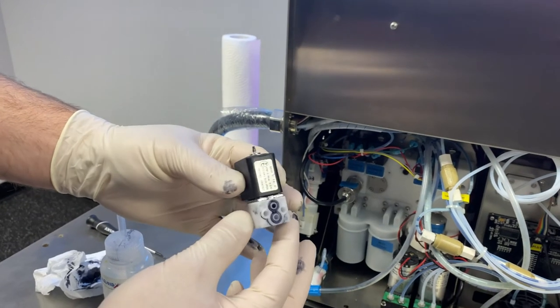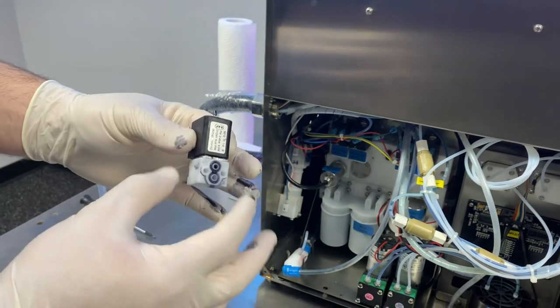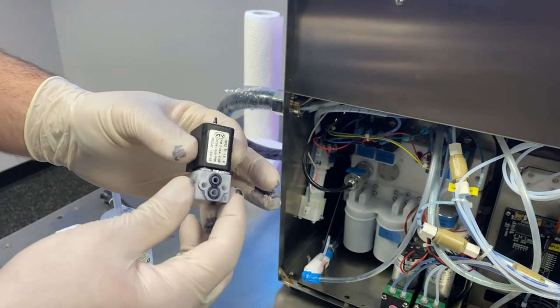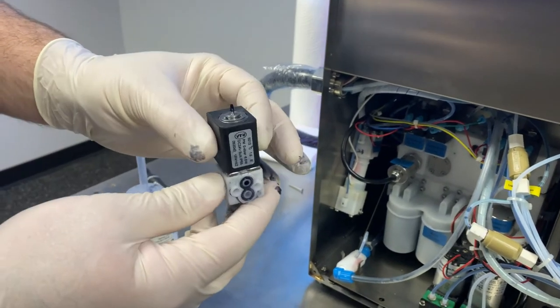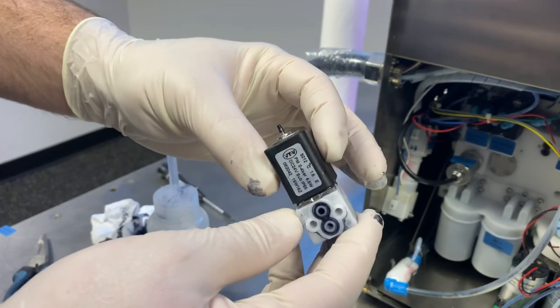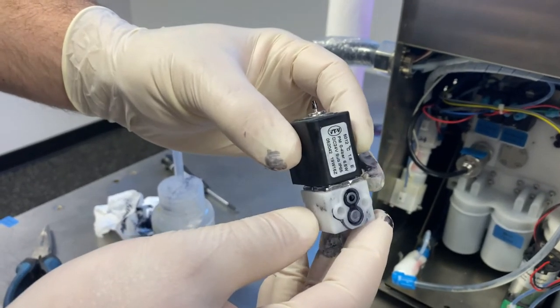Now what we want to do is take the solenoid off of the valve so we can access the plunger assembly and make sure that's not stuck. Realistically, that would be the most likely cause if this valve weren't working, that plunger being stuck.